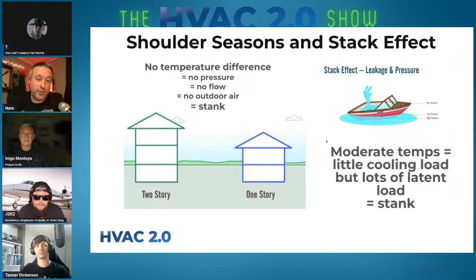And the other thing is, if you're in a humid climate, moderate temps lead to little cooling load. If it's 72 degrees out, like it was here today, oddly enough, but the dew point's 65 degrees, you still got some latent work to do. So there's lots of latent, but there's almost no sensible cooling load to do. So that also leads to stank. Today was remarkable. I checked the dew point. It was 32 degrees. I've never seen a 32 degree dew point on a 70 degree day. Never seen it, but I don't normally see 70 degree days in the middle of winter either. So you can have that.